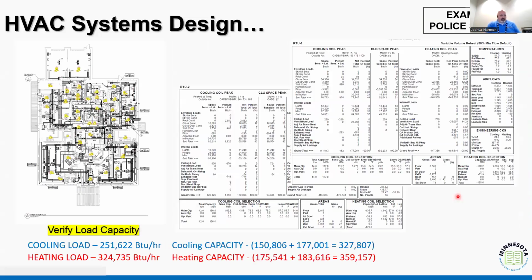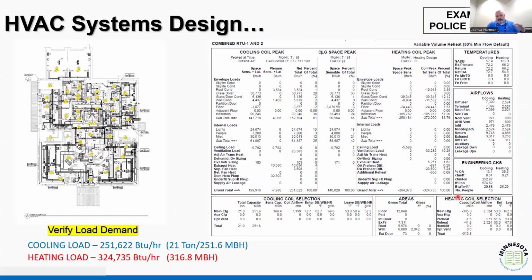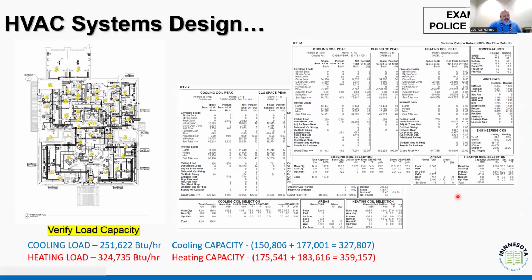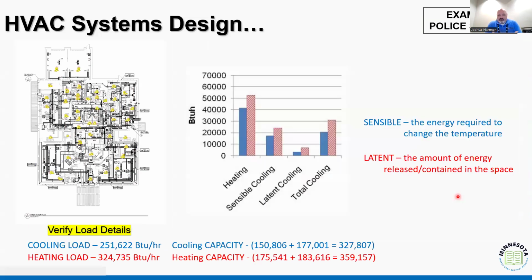So this one here used a design that provided both in a combined versus separated systems. So that again, we figured out if we have one system that has redundancy, then how do we demonstrate that, right? And again, this is something where I had conversations with the designers of this, and we talked about if we need to understand the redundancy so that we don't have this one direction mindset that says, wait a minute, I see you have 200,000 BTUs of need, but you're giving me 300,000 or 500,000 of capacity. Why? Well, let's talk it through and let's have that conversation.